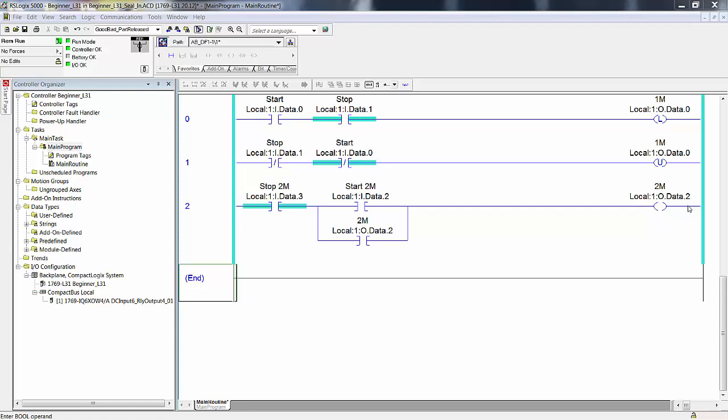Then we turn on input 2, and you see that the output is now on. Then we have you turn off input 2, and you see there's 2 right there. It's on, it's off. With this on and this off, this is still on. Now the reason it's still on is because of this OR. It's sealing itself in. The state of this bit is on. So when it reads the logic, true, false, true, turn this on. So this will stay on until you make this go false.